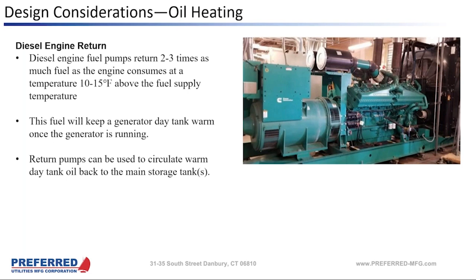Then they started manually turning on the return pump, and that circulated warm oil back to their main tank and helped them get their supply pumps going by warming up the fuel in the main tank. So in an emergency, if you can get a genset running, that genset is going to give you a source of warm oil that you can use to spread around through the system. It's going to have to be done manually. Our automatic controls aren't going to do this, but it's an option in an emergency.